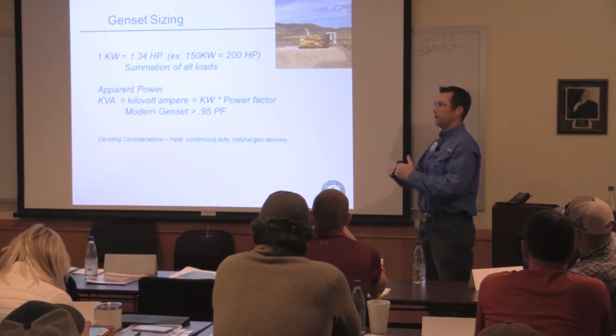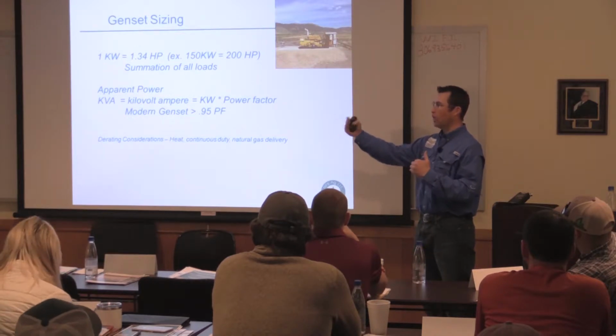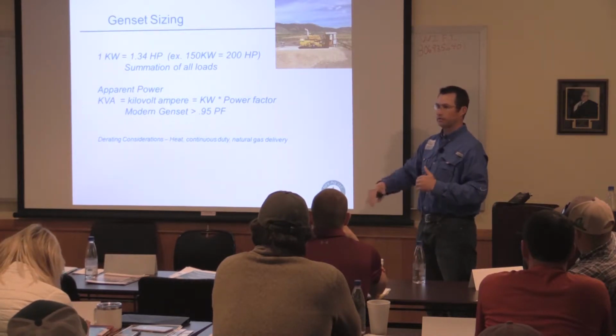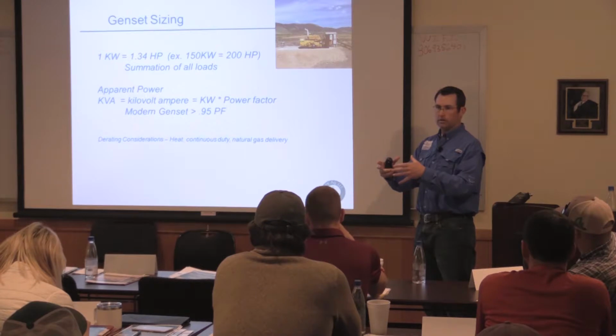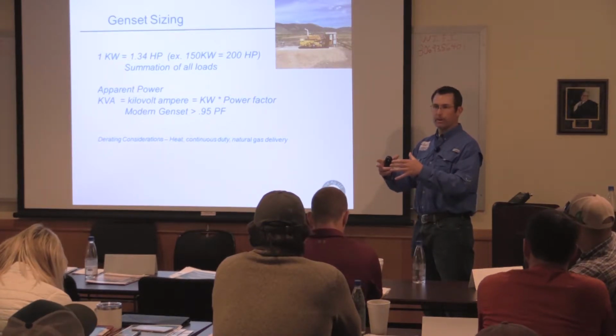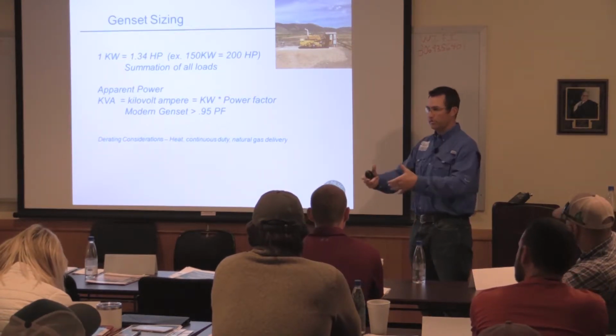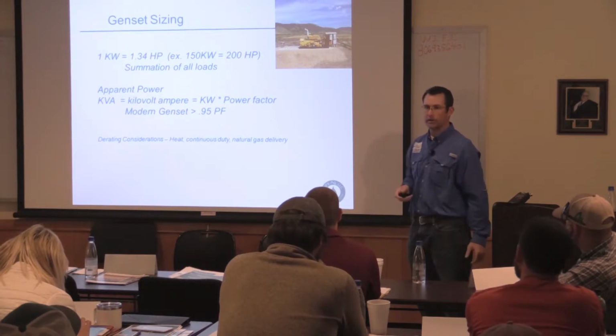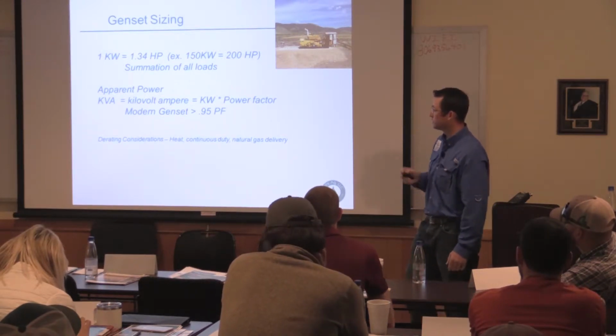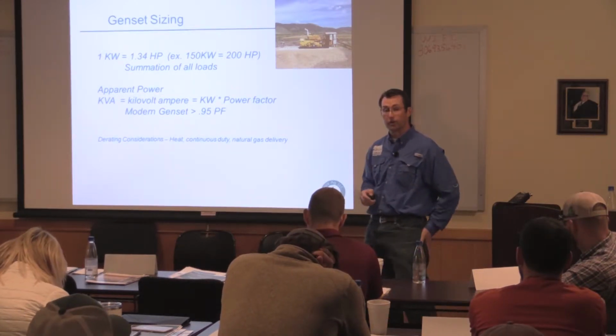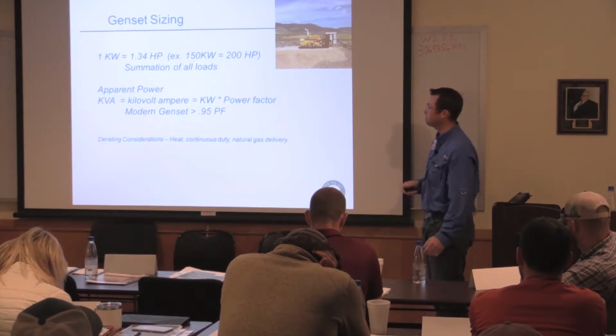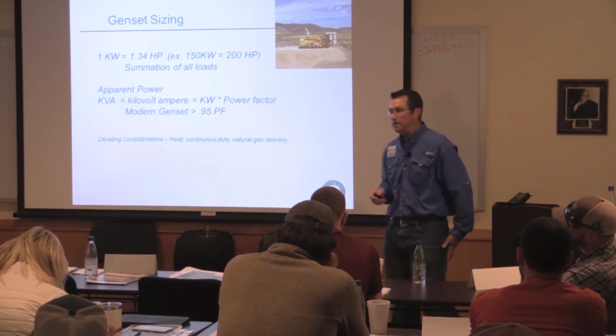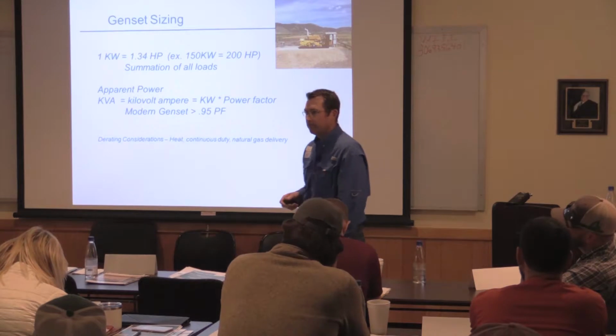Okay, you never get an improvement in power factor. It's always going to be a deduction. Okay, so you've got a motor that's loaded at exactly 40 horsepower, you're going to need to provide more than 40 horsepower to overcome whatever that power factor loss is. And I'll show you some nameplates where you can see where to find power factor on there, because it's very important in this sizing. What are the power companies generally give you insofar as that power factor?